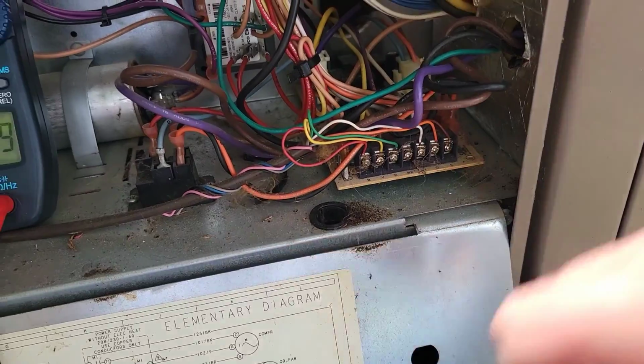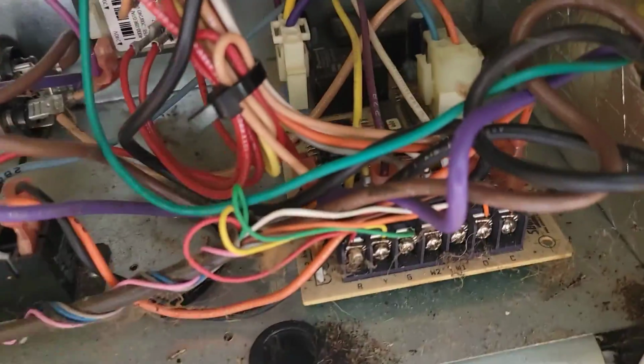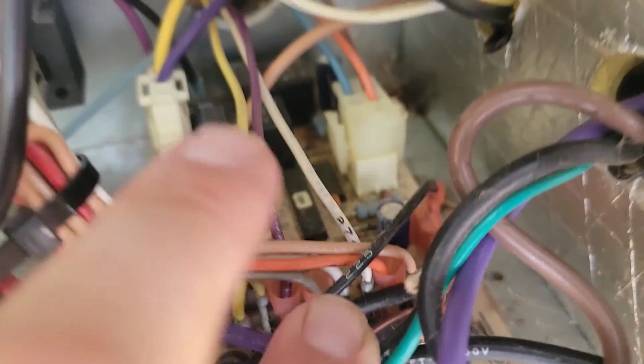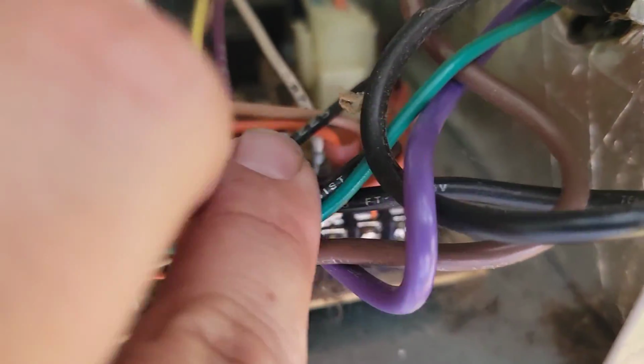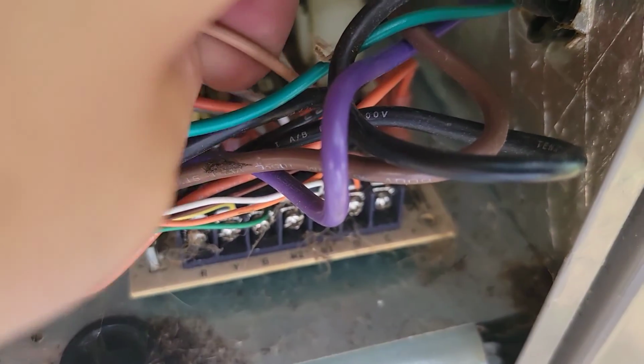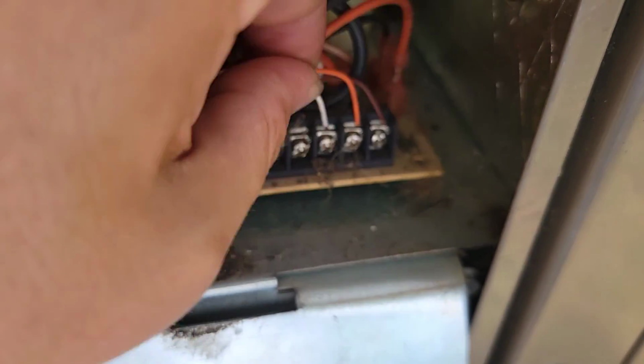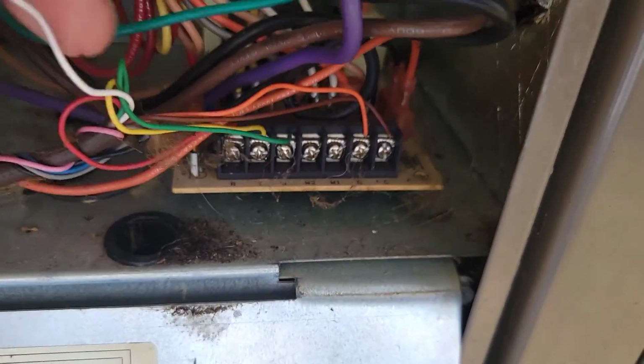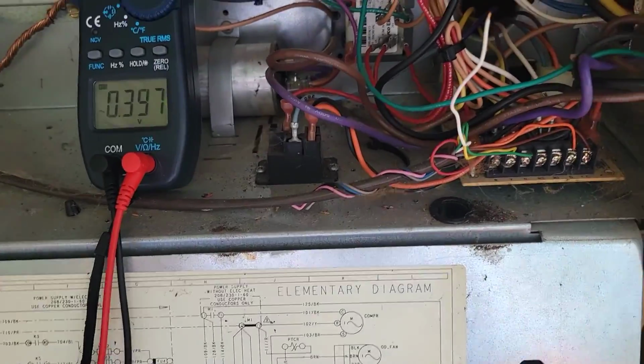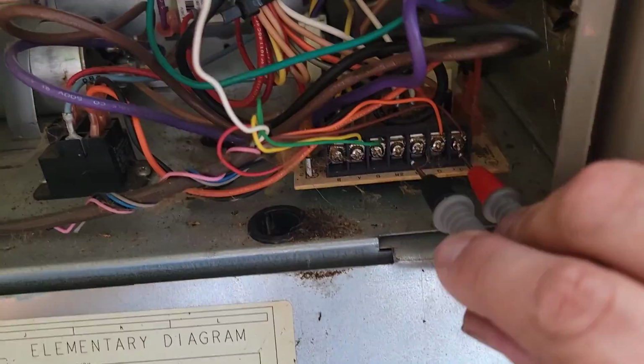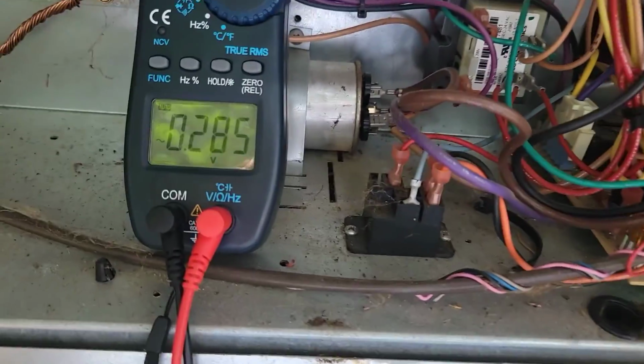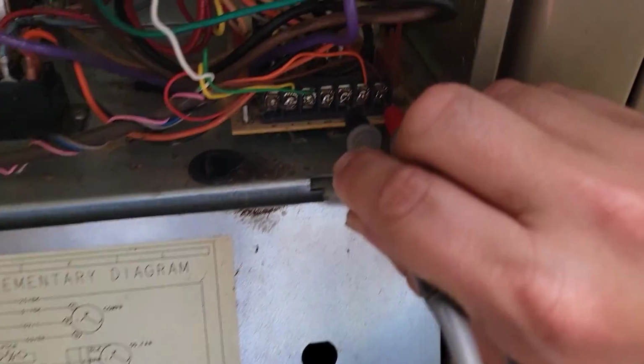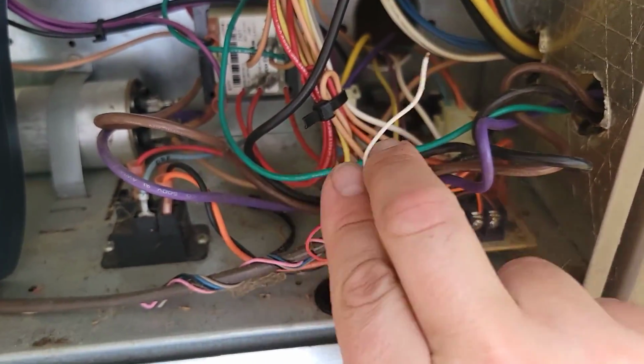So I wonder. You see, hold on a second. See this board? It's got a couple wires going to that terminal. Well, I'll tell you what, I can just take this wire off and see if the call goes away. If it's coming from the thermostat, I'm just gonna take that off. I'll resplice it, put it back on there. So I took that wire off. C to W. Is it still there? No, it's not there. It is not there. So it's coming from the stat wire.